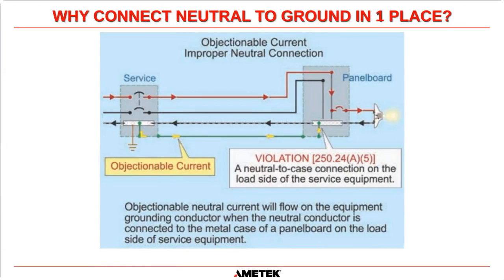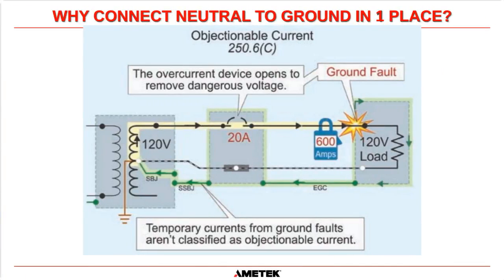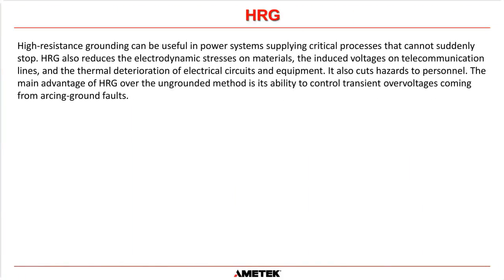But if you connect your neutral to ground here and your neutral to ground here, in normal operation, depending on the resistance of the neutral conductor to this panel board and the ground conductor to this panel board, some current in normal operation will be allowed to flow back to this neutral, and that's detrimental to the system, and that's a violation of code. So that is why you should never have a neutral connected to ground at 2 points within a system, which is why you have to remove that jumper in the system. Okay.